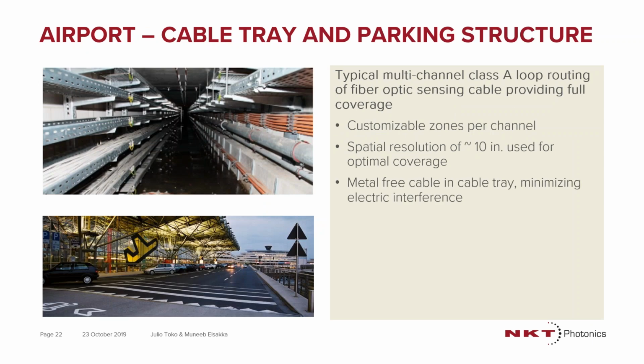As I discussed, cable trays for airports is an example. We've done also areas where you have a parking structure where, if you decide to really, from a big project point of view, run fiber optic linear detection, it can have an advantage over running some smoke detectors, simply because you don't have to bring the current, or you don't have to do the electrical connection to each one of them. So you can do a Class A loop, and then you can really protect your assets in multiple areas.